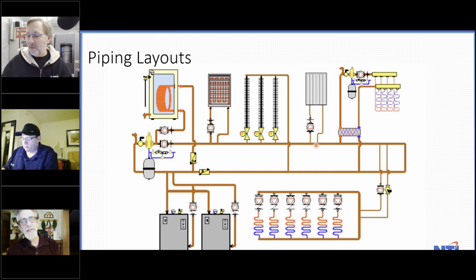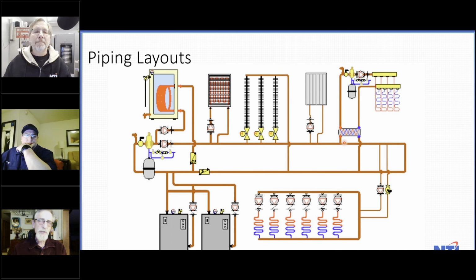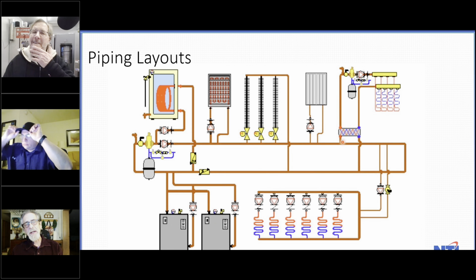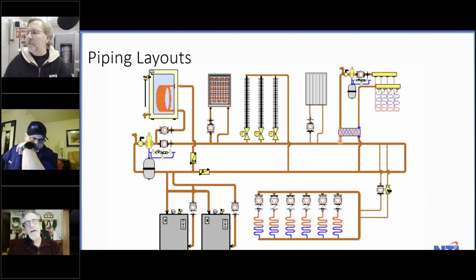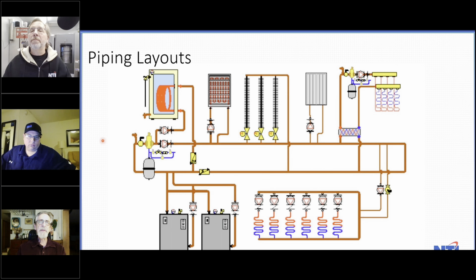Well, the other thing on this is that anytime you lay out one of these multi-temperature, multi-zone systems, you want to think about what wants the hottest water and what could use the coolest water. So as you go around that primary loop, your temperature is being decreased by each previous load. Of course we've got our own pump for the indirect, so that's getting whatever temperature the boiler is designed to put out for the indirect. But then the air handler gets the hottest temperature, the baseboard gets the next hottest, panel radiator a little less than that because typically they don't need to run as hot.